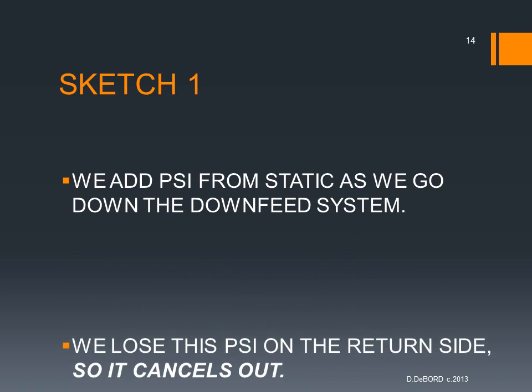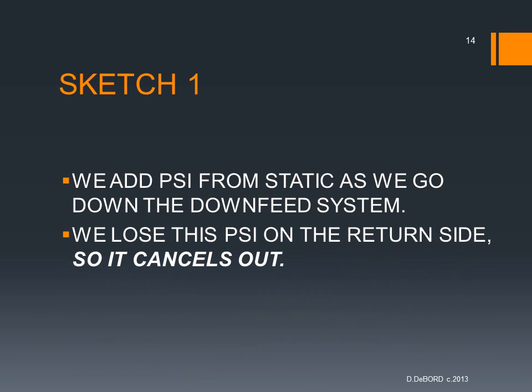We add PSI from static as we go down the downfeed system. We lose this PSI on the return side going back up to the heaters, so it kind of cancels out. So you don't have to account for that pressure to get back up because you picked it up when you came down, and then as you go up, it goes down. The pressure is reduced till it gets to the top.